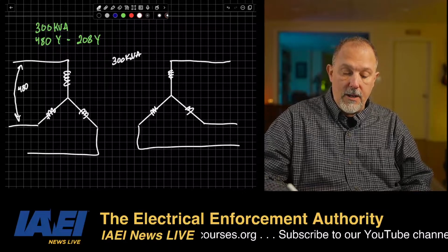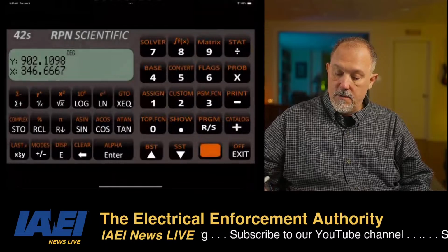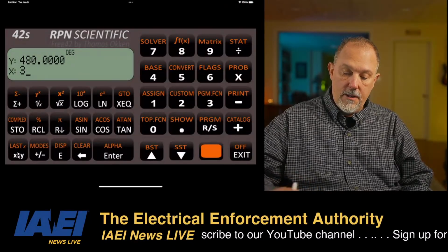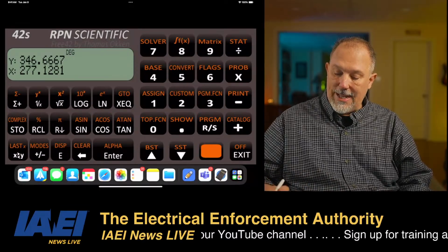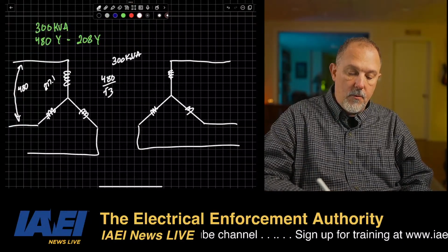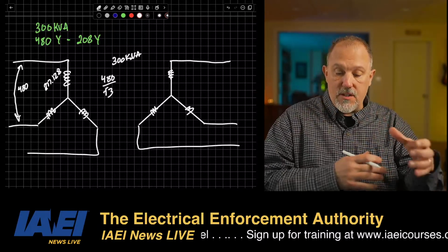It's 480 over the square root of 3. 480, 3, square root, divide, 277.128. So 277.128 across each of the primary windings.